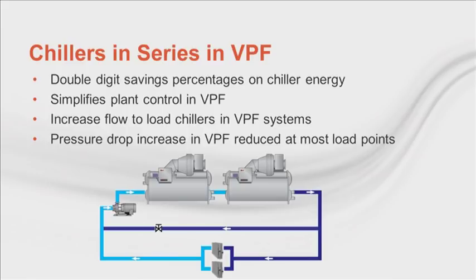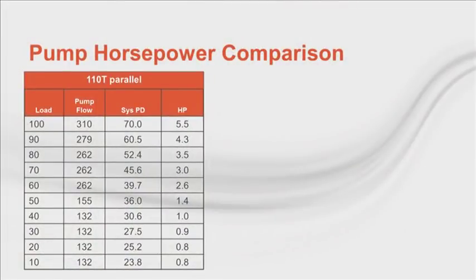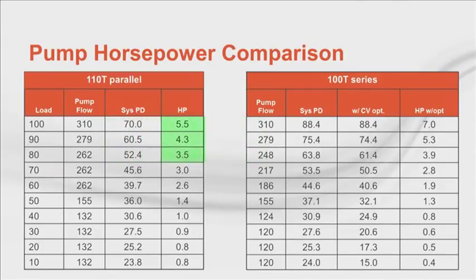As we illustrated in detail in 2008, the minimum flow bypass also plays a role in keeping our parallel configuration online. So we must look at all the components of the pumping energy rather than looking specifically at the evaporator pressure drop. Because we don't have to bypass for minimum flow, pump flow of a series system is actually lower at most loads. Now, let's see the impact that has on the pump horsepower. On the left, we have the parallel chillers. Note that the green boxes identify the times when the pump horsepower is lower. Pressure drop through the chiller drops with the square of the flow rate. So, even with a higher initial system pressure drop through the evaporator, it evens out very quickly.